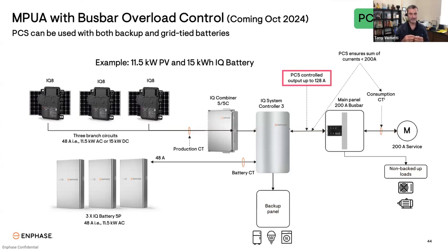A workaround, and I'm not talking about PCS, but with regular battery installations with consumption CTs installed, a workaround that can be used if PCS isn't used is bundling all line ones together and going through one CT, and bundling all the line twos for the loads I'm talking about together through the other CT. That way you can capture all the loads. That is not a reliable enough method according to our engineers for Busbar PCS, because of the chance that mistakes might be made. All the bundling might not be done correctly. Maybe not all loads that are in the panel are actually bundled. So for that reason, just to reiterate, with Busbar PCS, you really do have to install the consumption CTs on the main feeders going into the panel.